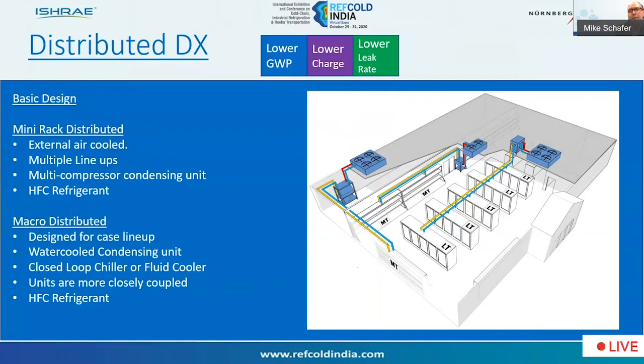Another variation of that, closely coupling the system, would be a macro-distributed, where in this case you'd have one condensing unit for a lineup. Now, these would typically be water-cooled condensing units, where the heat rejection would be through a plate heat exchanger. You'd have a closed water loop system, either to a chiller or to a fluid cooler. And the advantage of the system, once again, is to more closely couple the refrigeration equipment with the load or the cases. Then typically systems would have HFC refrigerants.